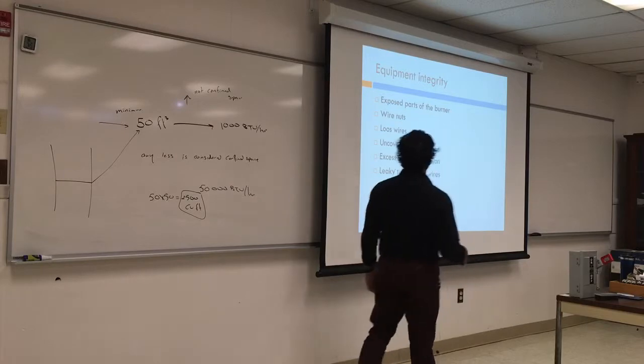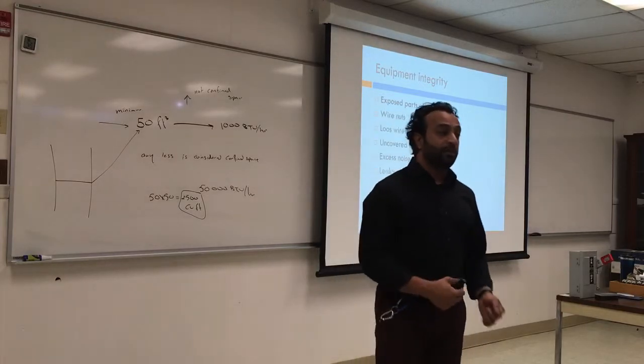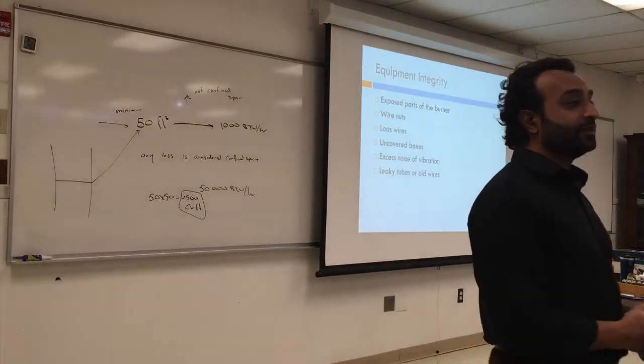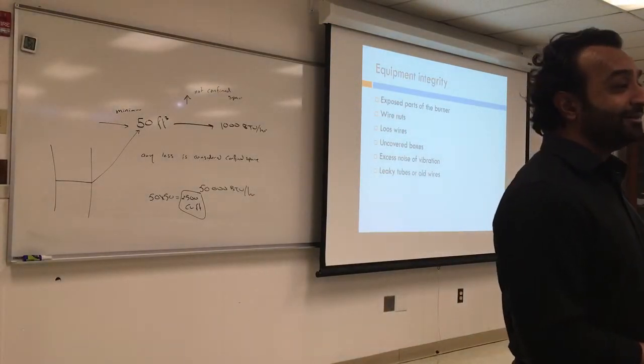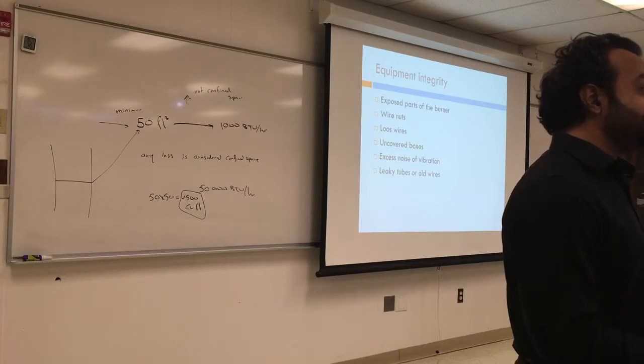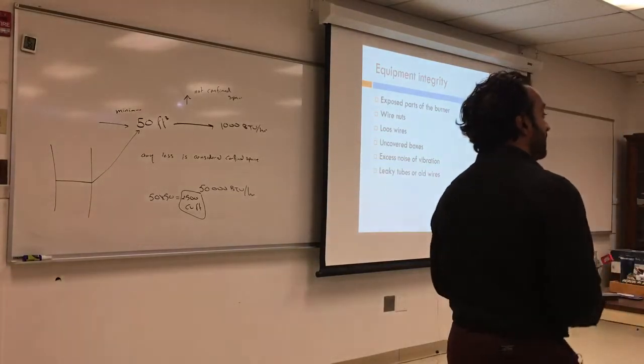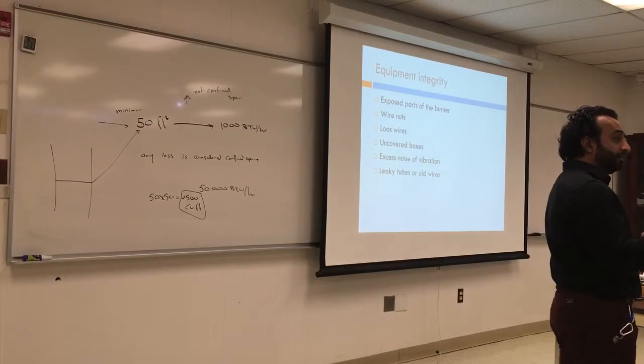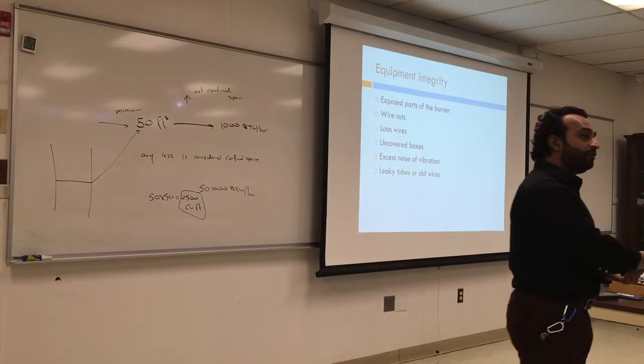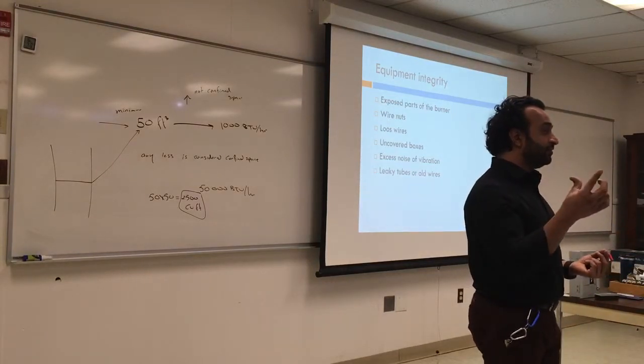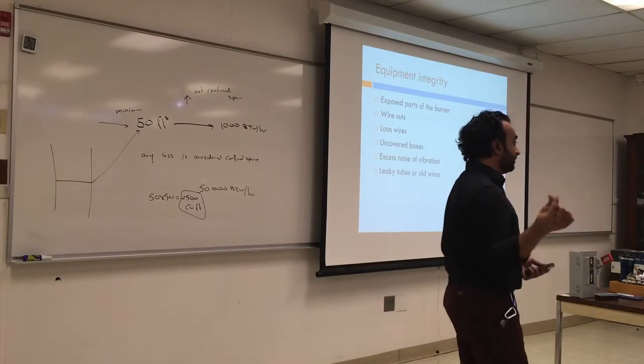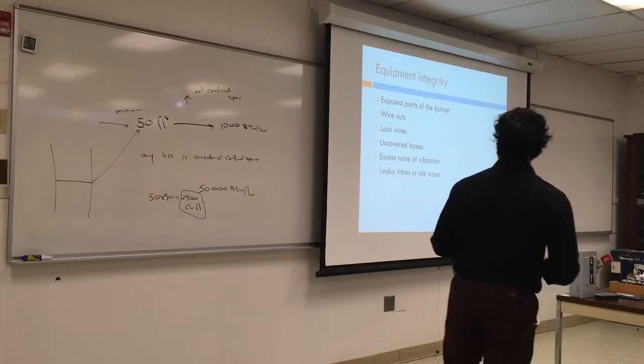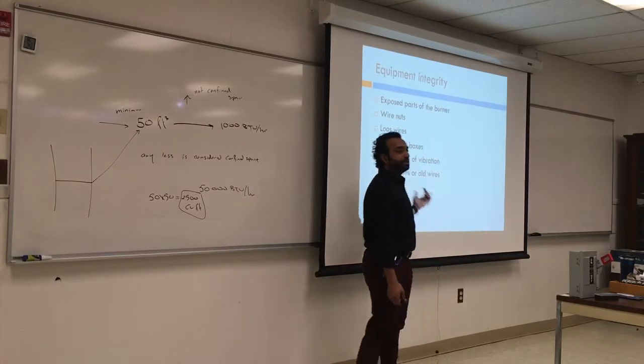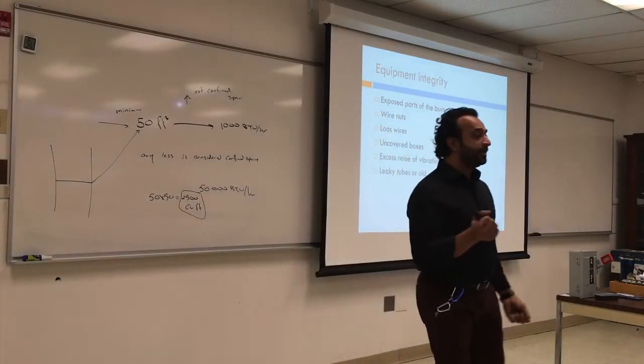So, vibration, leaky tubes, or old wires. This is very important. Check for old wires. If the wires are covered with fabric or paper, or it's very old or crispy, it's time to change them, or at least report them. If you bend it and you feel pieces of the insulation falling apart, that has been too old and it's time to change it. If you run your fingers through the wire and it sticks to your finger, it's really melting and you should change that wire. Leaky tubes should also be changed, and go with a flashlight and inspect the tubes for kinks and bends.